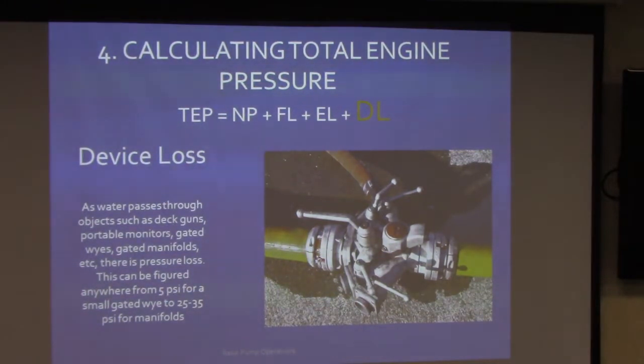For example, the piping through the deluge gun on the truck is usually about 20 psi for 500 gallons per minute. So, very simply put, if you're going to flow 500 gallons per minute from the deluge gun or the deck gun, whatever you want to call it, you've got to be at least at 100 psi.